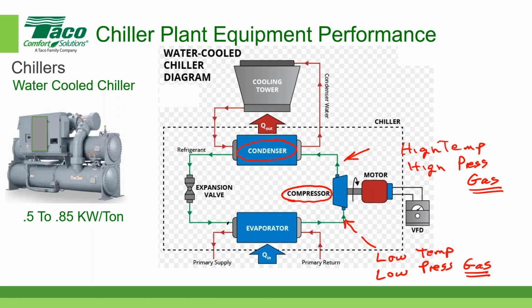In the next slide, I'm going to show some temperatures. And then it turns from a high temperature, high pressure gas to a high temperature, high pressure liquid. So it leaves the condenser as a liquid again, at the same high temperature and high pressure, but this time it's a liquid. When we look at the pressure enthalpy diagram, you'll see that the refrigerant process across the condenser is a constant pressure process.